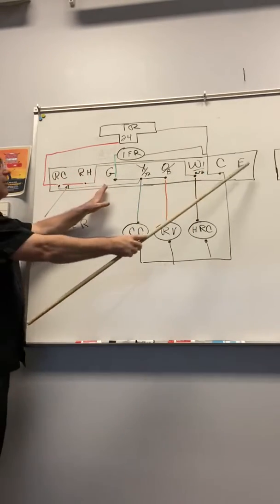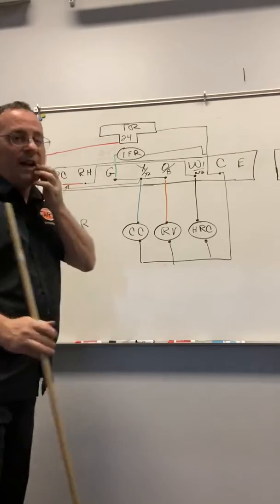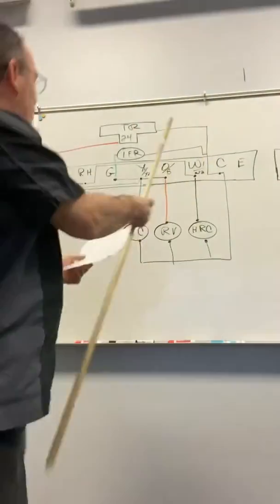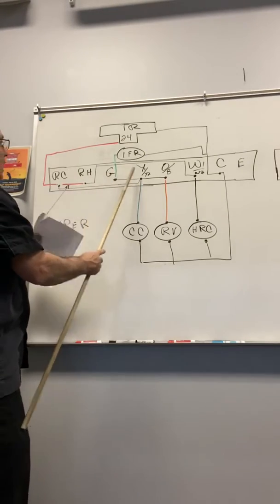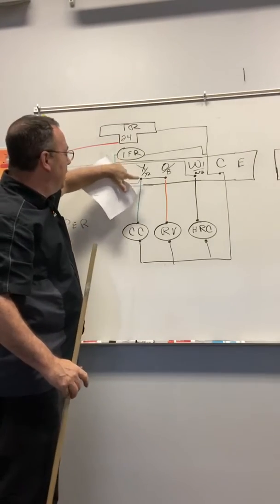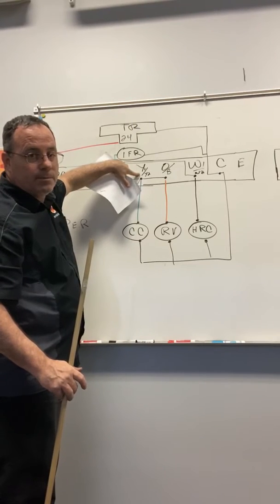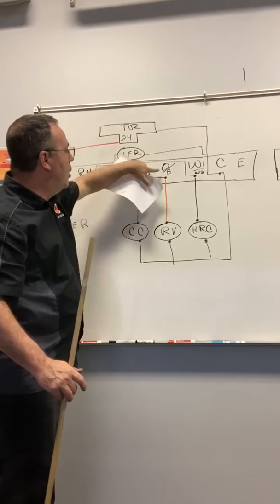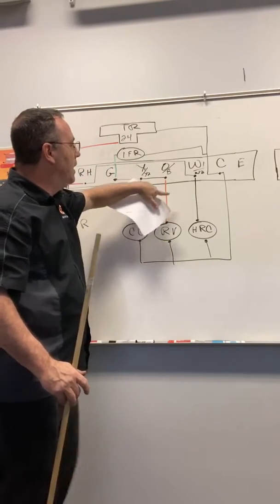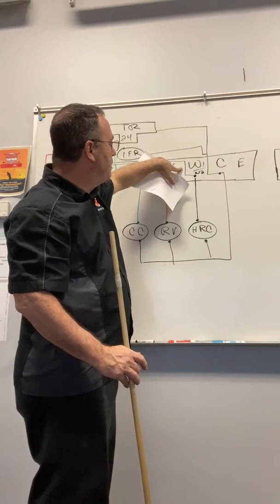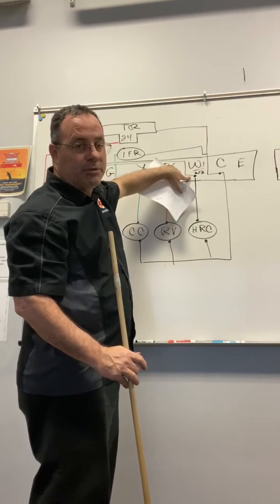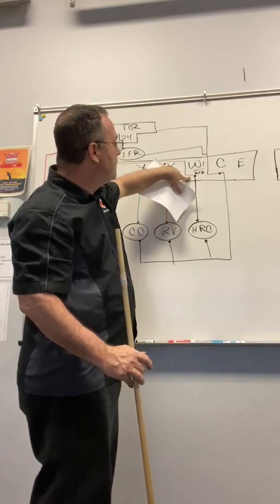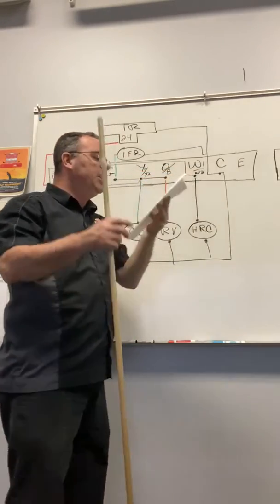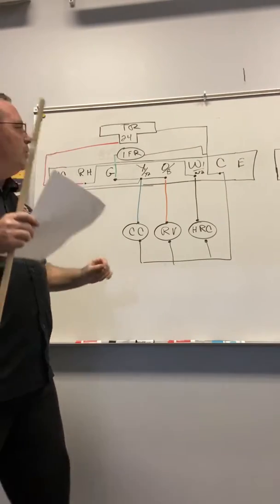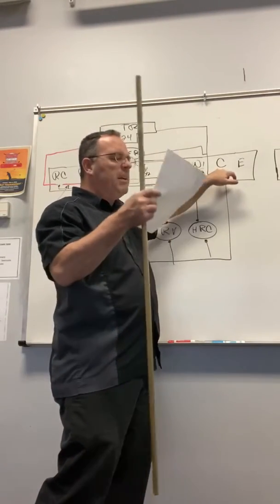So that's first stage cooling, second stage cooling, first stage heat, second stage heat. Normally these colors are about the same. I wrote them down right here. R is a red wire, G is the green wire, yellow for Y, but they'll use light blue for Y2. O is orange, and B too. White is used for W. They'll also use brown for W2. Common, they usually use dark blue or black. E has no universal color.